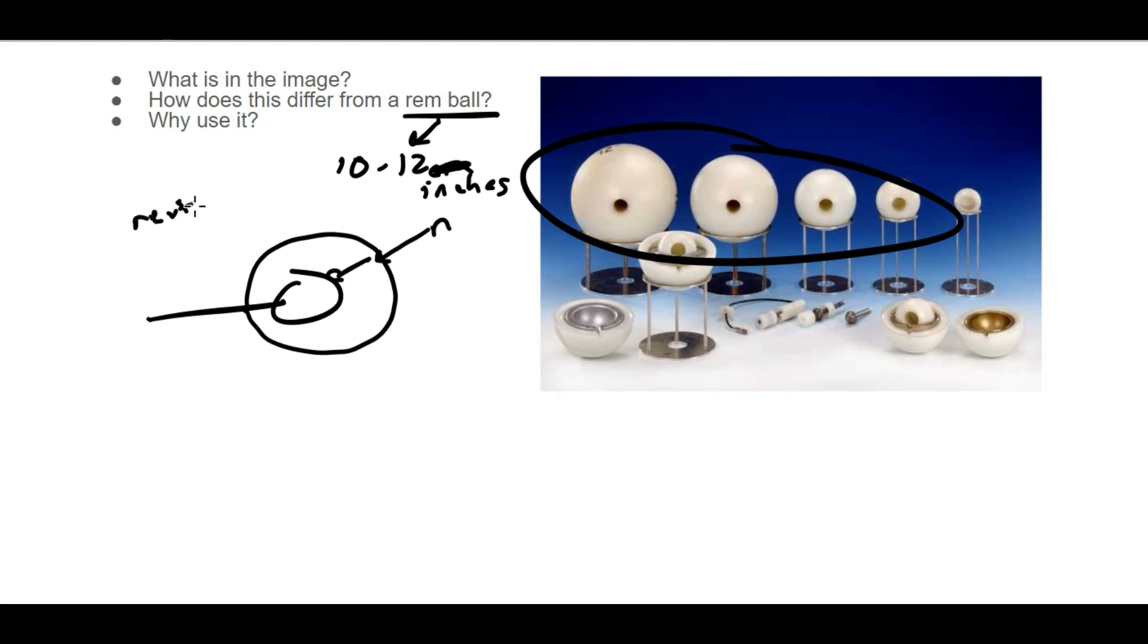Bonner spheres have really good gamma ray discrimination. Their range is from background all the way to grays, so great for shielding. If you have high levels of neutron dose, it will be able to detect it. It also measures dose equivalent, which is really nice.